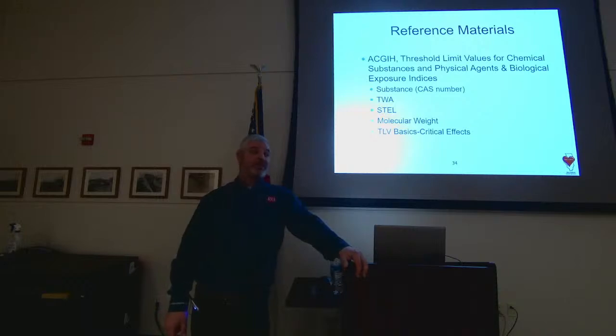But if that value keeps returning, oftentimes they'll say, hey, your device isn't working right. That very well could be. When was the last time you calibrated that, sir? Well, about a year ago. Well, you need to calibrate it. So we send out a service tech and he calibrates the instrument, and it calibrates just fine. He turns around and leaves.